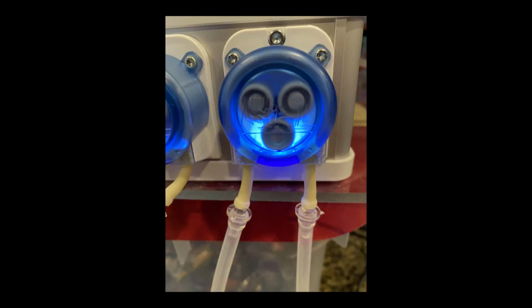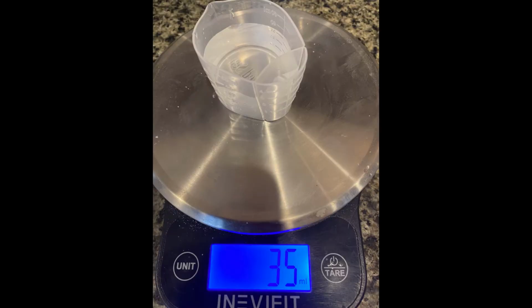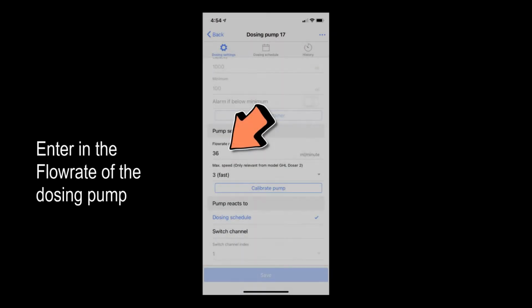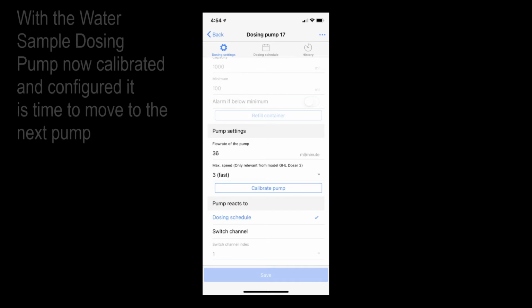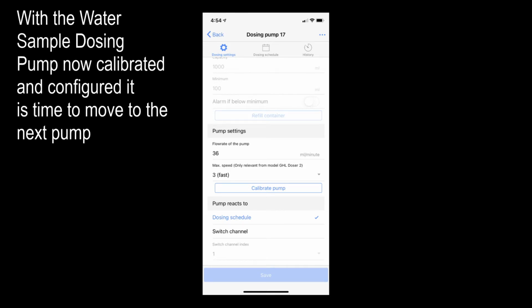Then I run the calibration by placing a supply line dosing tube to the doser into RODI water and the excess side of the doser into my collection container. Once the calibration is done, I place the collection container onto the scale and record the results. I will do this 3 to 5 times depending on the results, taking the average and then entering that number into the flow rate of the pump. Once I enter in the flow rate of the pump, I click Save. With the water sample dosing pump now configured, it's time to calibrate the reference A pump.